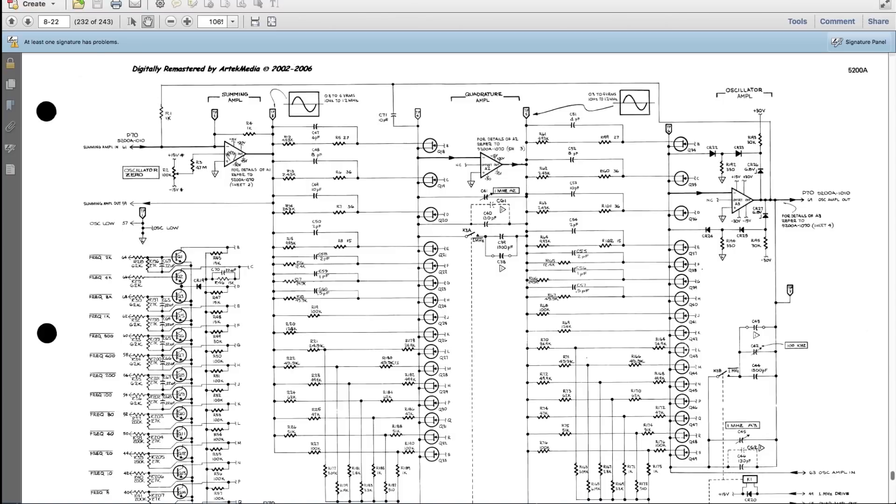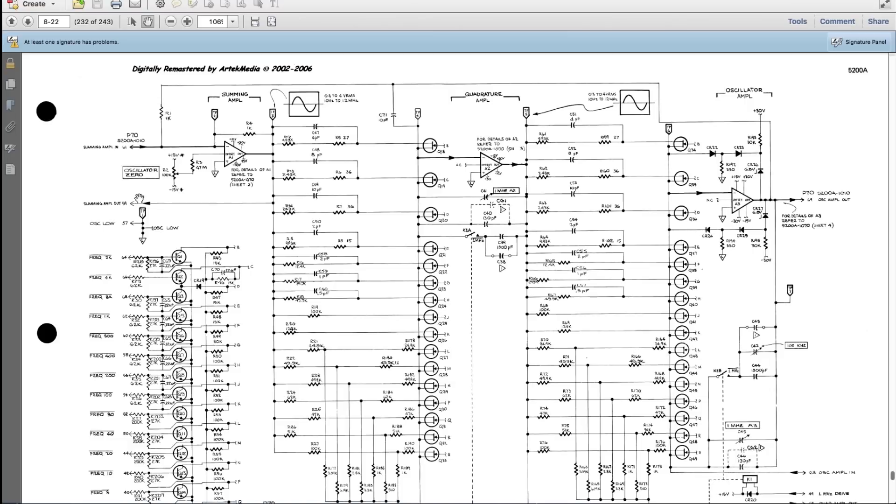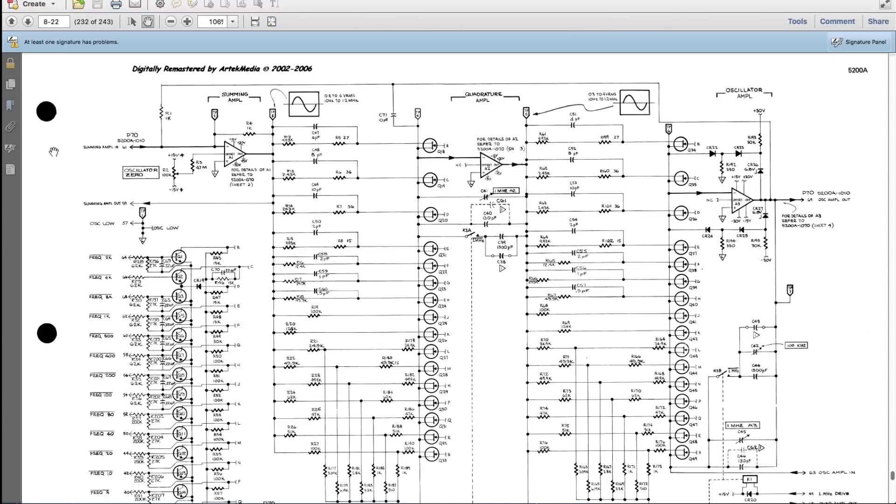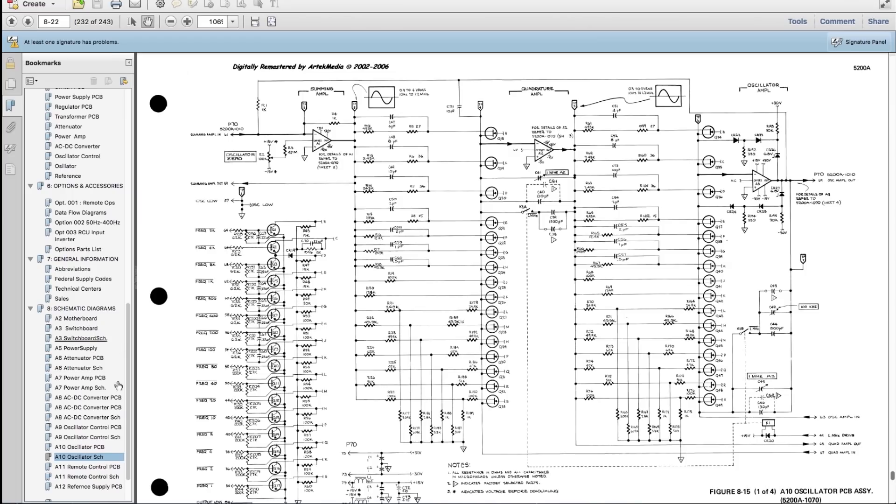Now, this has some other aspects along with it. There's a summing amplifier out here, which is in parallel with the device. Summing amplifier in, summing amplifier out. They go to the oscillator control board. It gets a bit more complicated, but they actually have a capacitor across it, which is used to tune this response. There's also an oscillator zero here. I've tried adjusting that. It doesn't seem to change anything. So let's just look at the summing amplifier out and summing amplifier in. Let's see what those do. Those are on the control board.